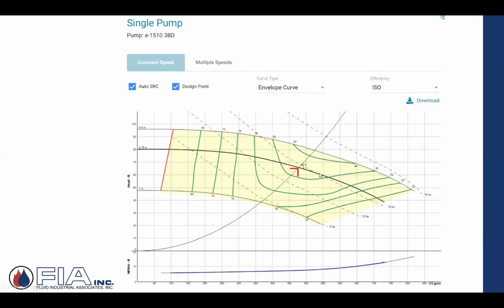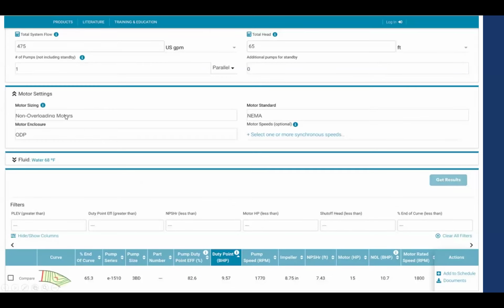And the reason it might drift out is this: I might not have 65 feet of pressure drop in that system. It might be something a little bit less than that to get that desired flow rate. So if I'm 60 feet of head, and all I'm looking for is that 475, but I'm staying on this curve, I might drift out past that 10 horsepower. So to protect myself, as a good selection, I'll probably type in my software, right up here in the motors, pick non-overloading as an option.